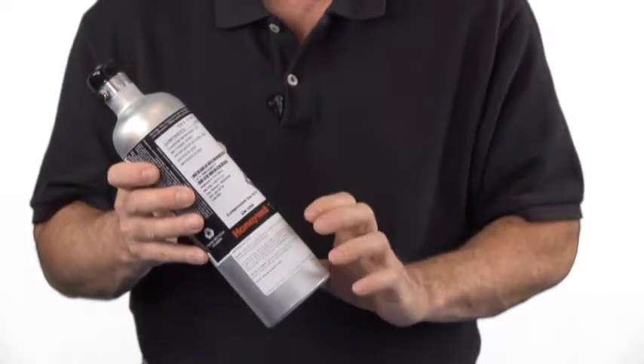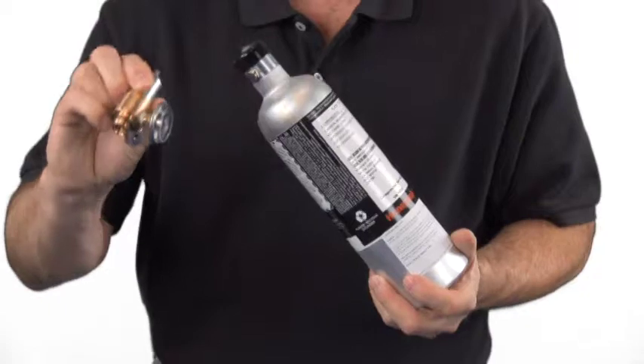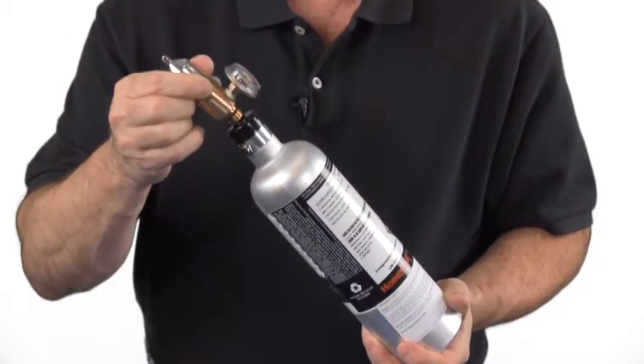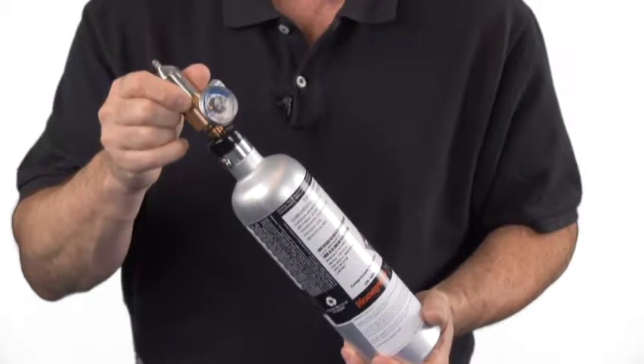And to apply it to the instrument, we're going to use this regulator. We use the calibration adapter mentioned earlier. And since it takes about a minute to calibrate, and this holds about 34 liters, you're going to get about 30 calibrations.